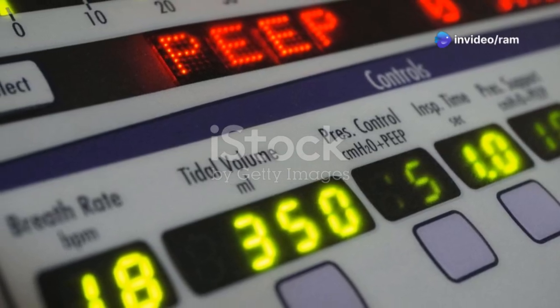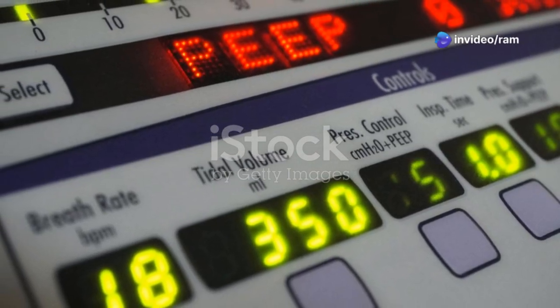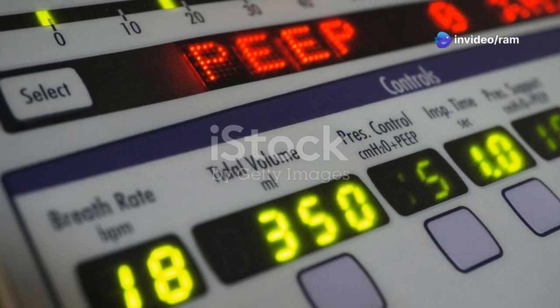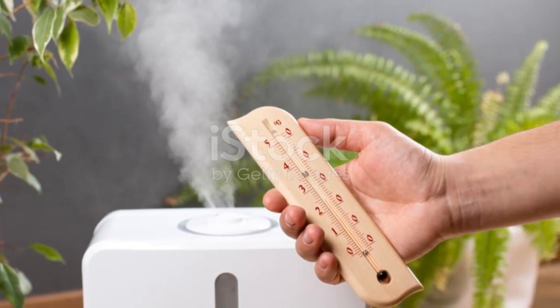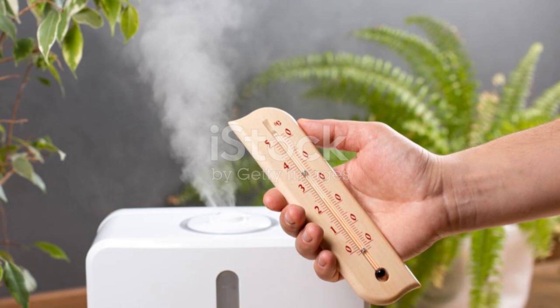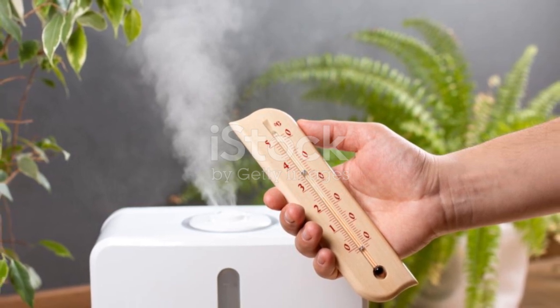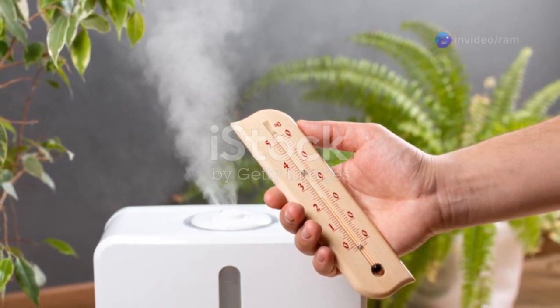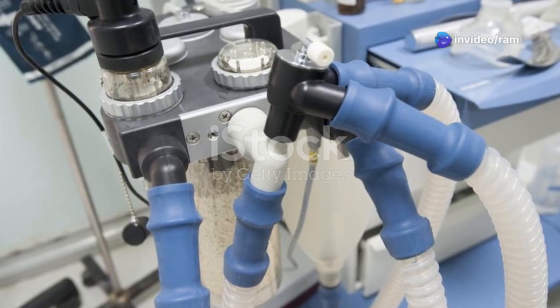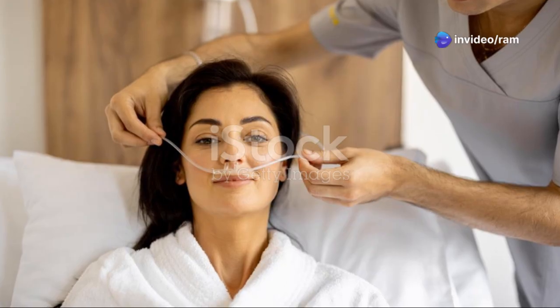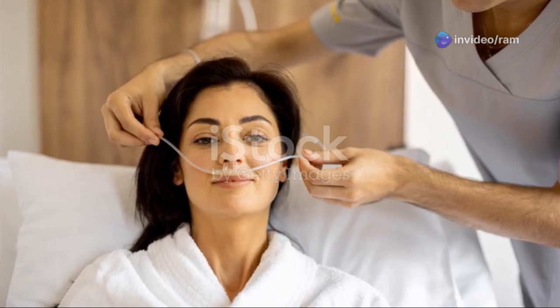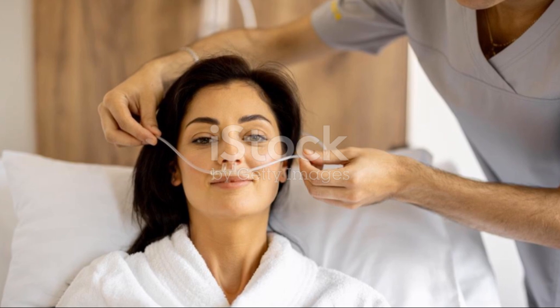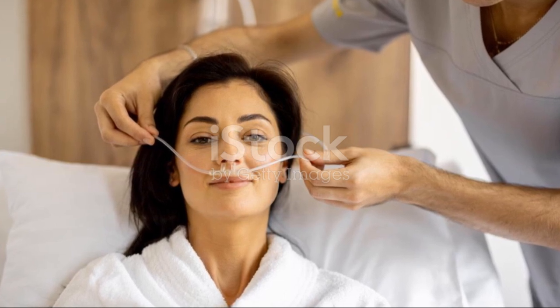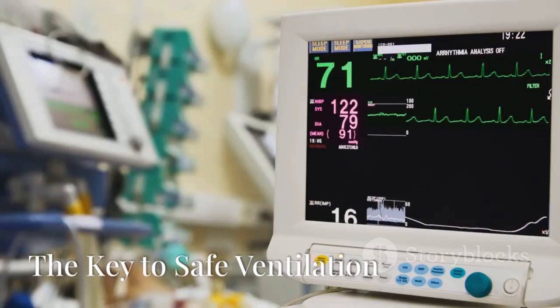Fine-tuning for comfort. Once the ventilator is up and running, the settings are adjusted to ensure patient comfort and adequate ventilation. This might involve tweaking the pressure support, adjusting the flow rate, or adding humidification to prevent the patient's airways from drying out. Setting up a ventilator is not a one-time event. It requires ongoing monitoring and adjustments to ensure the patient is receiving the right amount of support and to avoid potential complications.